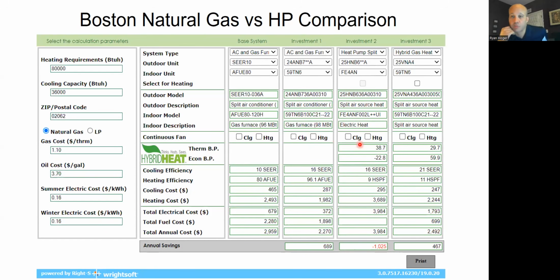Mark types in, have you worked with customers who have also used kW demand to manage changeover on dual fuel systems, i.e. set a limit at some measured whole facility demand number? I have not, and mainly because most people's demand is coming off of their summer bill, right? And then you're paying that for an extra 11 months of penalty. You do have demand charges that are also your monthly demand charge, but usually the big dollar amount one, at least where I live, is the peak that happens in the summer. So shedding kW load in the winter doesn't really do much for me. Now, if the building starts using a lot of heat pumps, right, and it's a heating dominant building, then that math would change.